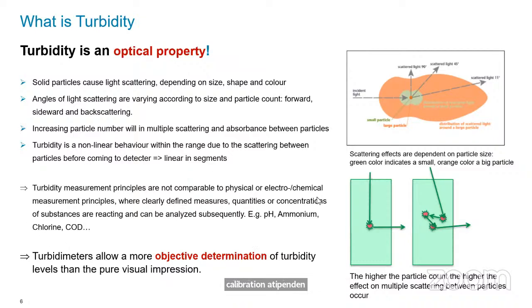So the most interesting fact is, if you think about other measurements like photometry or pH measurement, what we need here is completely different, because it is just an optical property. You just notice, for example, sand in water, which is just something fading out the light. So turbidity is not comparable to other physical or electrochemical measurement principles. If you think about pH, you have hydrogen protons, which define pH. And if you think about photometric concentration measurement, you know that there's a clearly defined concentration of a substance like ammonia. So the parameter ammonia is defined by a chemical reaction, and you know exactly how much it is.